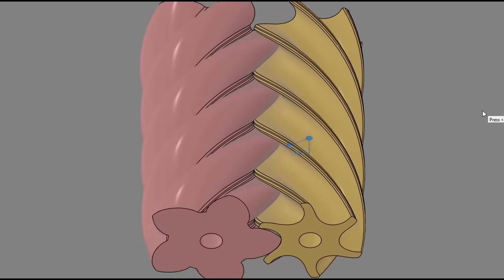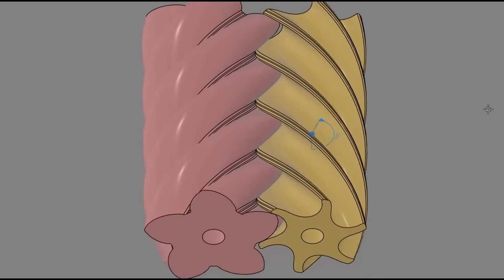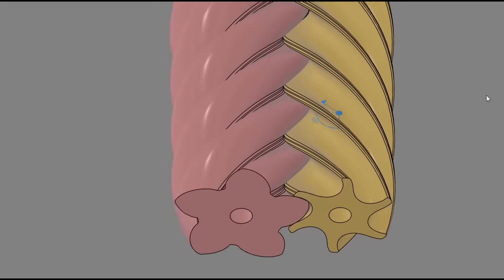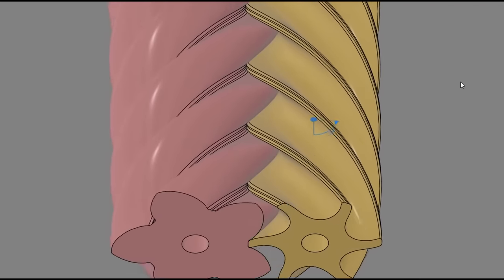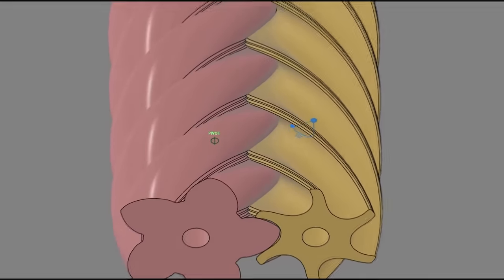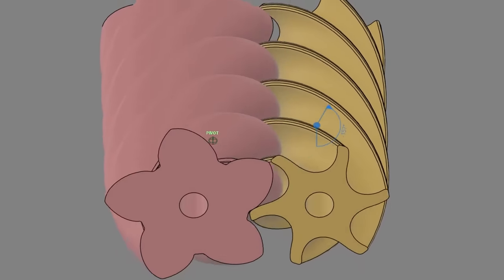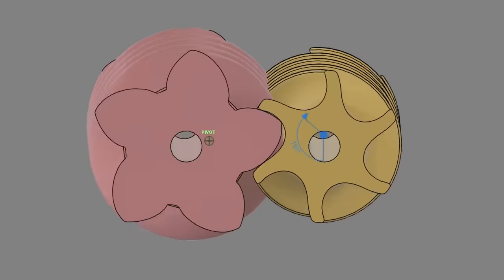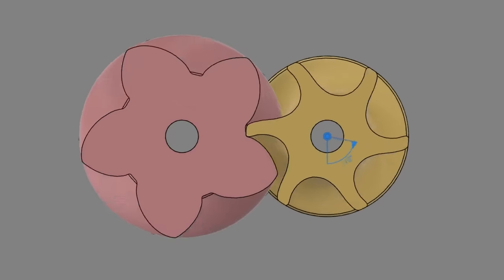The other cool thing about twin screw compressors is that the rotors actually form a pair of cycloidal gears. So even though the main rotor is larger in diameter, it has fewer lobes than the gate rotor, so it'll actually spin faster. And since there are five lobes on the main and six on the gate, this results in a gear ratio of five to six.